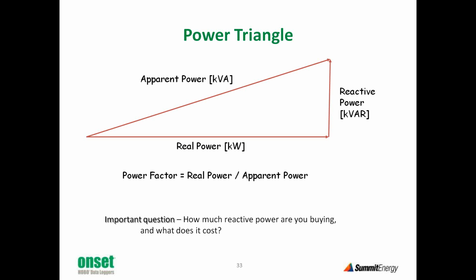Some of you may have heard the term power factor, and that's just the ratio of real power to apparent power. So if we had no motors and no inductive load, if we had only light bulbs and resistive load, you might imagine that this triangle would just be a straight horizontal line. There would be no reactive power, no kVAR. So the real power and the apparent power would be equal. And that's a power factor of 100% or a power factor of 1, or sometimes, to be fancy, we call that unity power factor. As you require more reactive power, the power factor will go down because that ratio of real to apparent will go down.